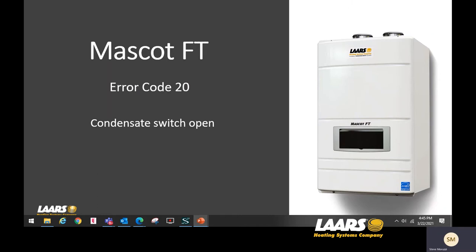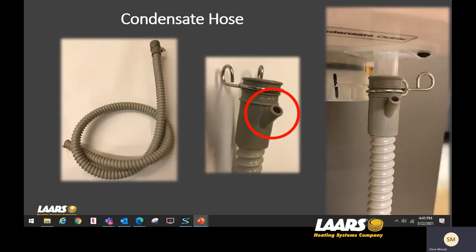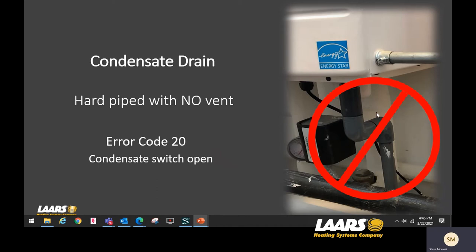Next we'll talk about error code 20 — condensate switch is open. Check your condensate drain, confirm there is a vent on the condensate pipe, and check for blockage or a blocked neutralizer kit. We provide a condensate hose with the Mascot wall-hung boiler that has a vacuum breaker and a clip. However, in some cases people have used hard PVC pipe with no vent, which will give us error code 20 — that means your condensate is backing up. You need the vent. In that example, a T-fitting would be needed extended up a little bit so water doesn't drain out.